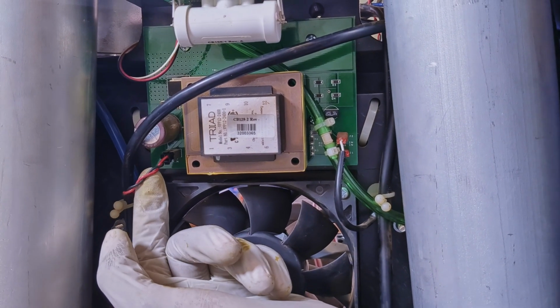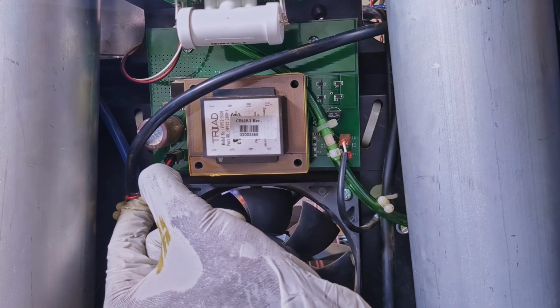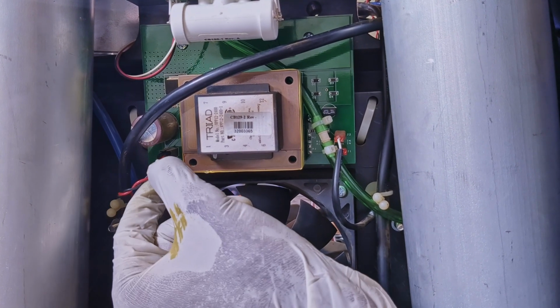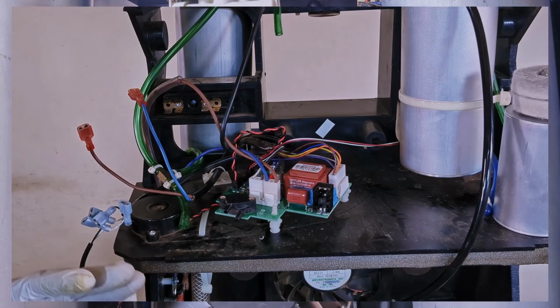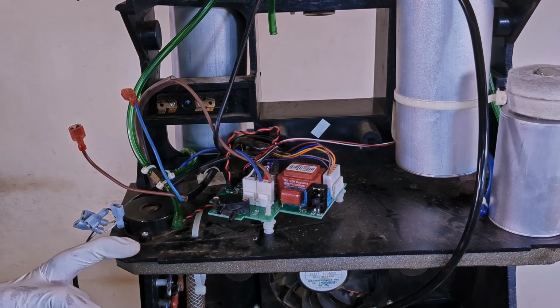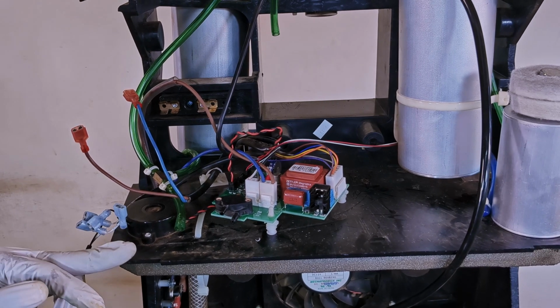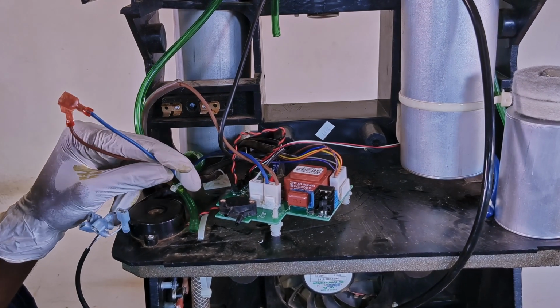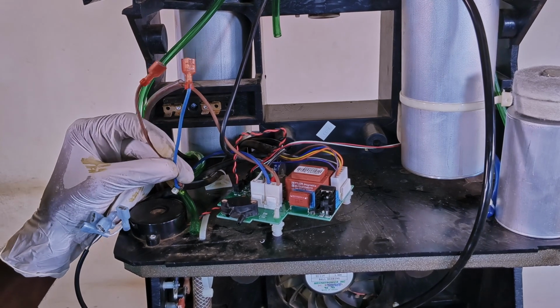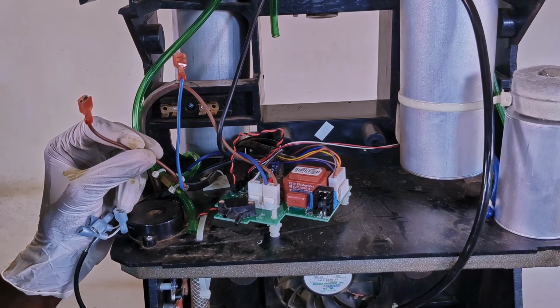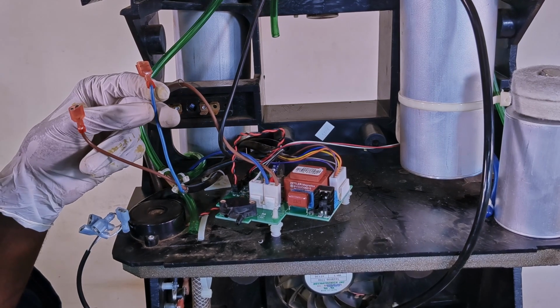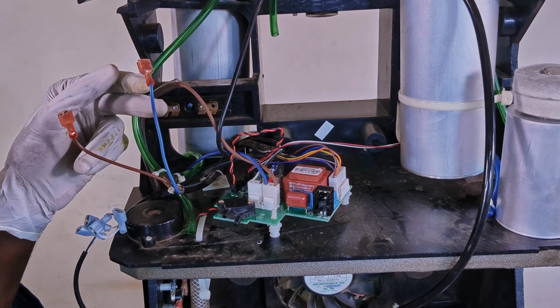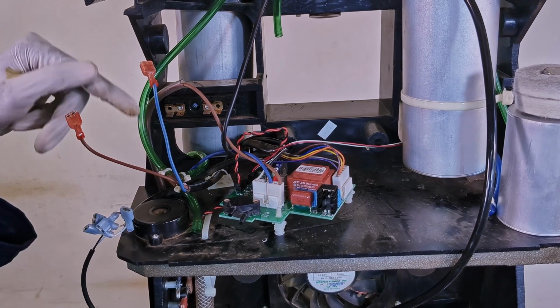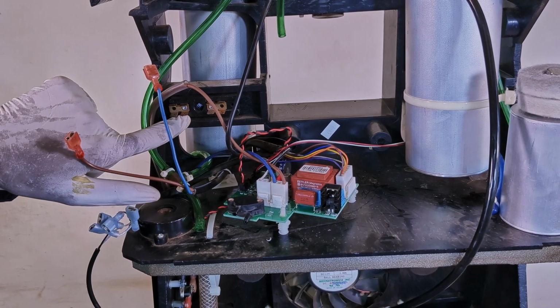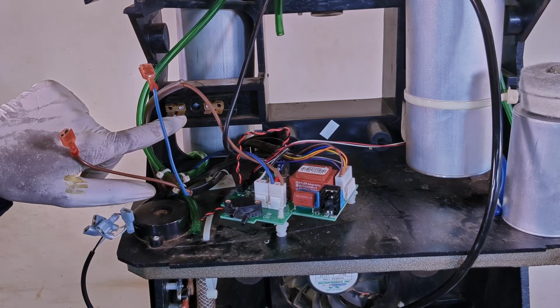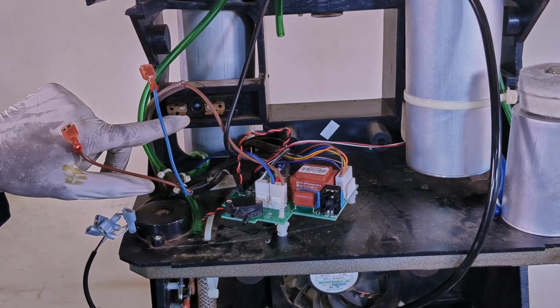These are the 2 cables that are used to supply power to the fan. The red one is the positive and the black one is the negative. As mentioned earlier, this oxygen concentrator operates on 230 volts AC. The 230 volts is supplied using this power cord. The cord has 2 cables. The brown one is the live cable and the blue one is the neutral cable. This neutral cable is connected on this side of the cable connector where all neutral cables are connected, and it provides a return path for current.